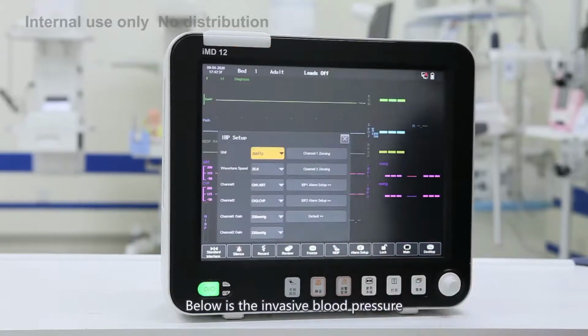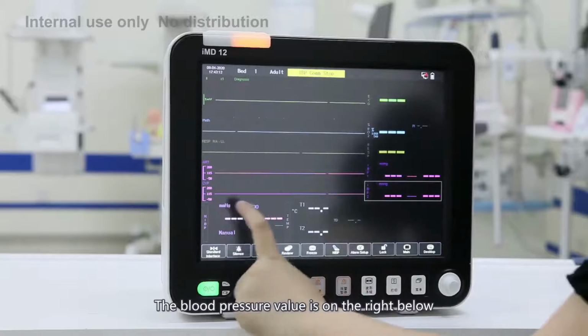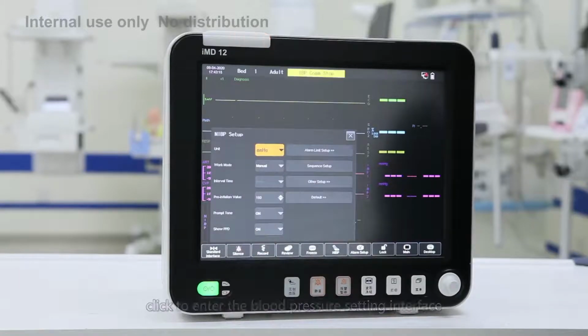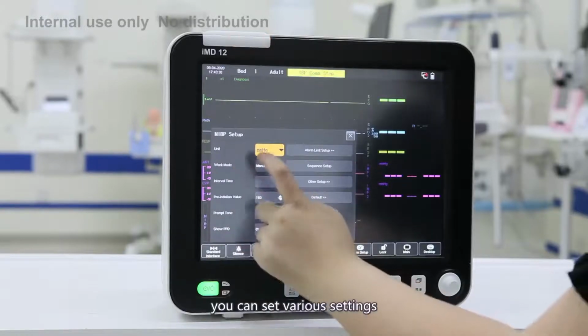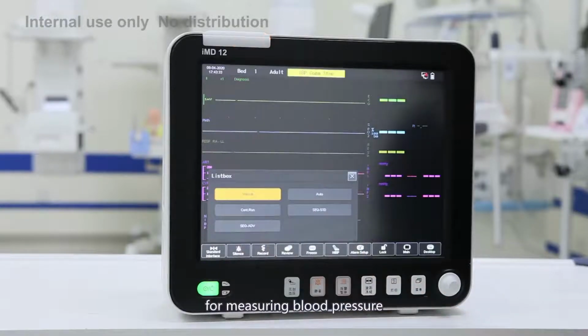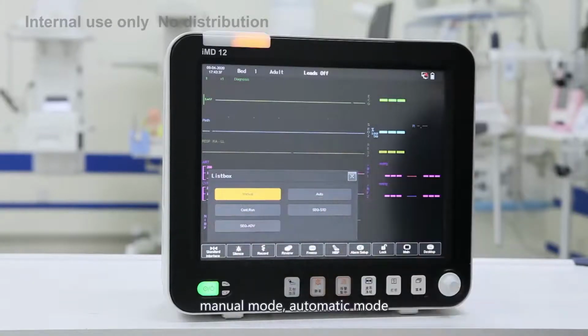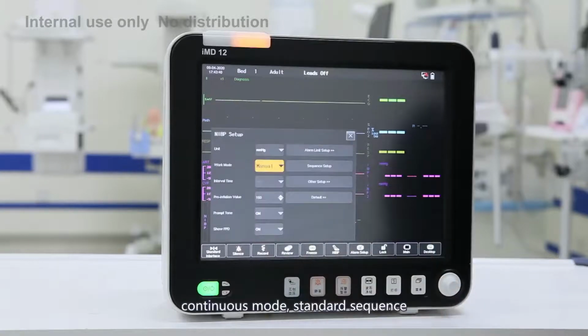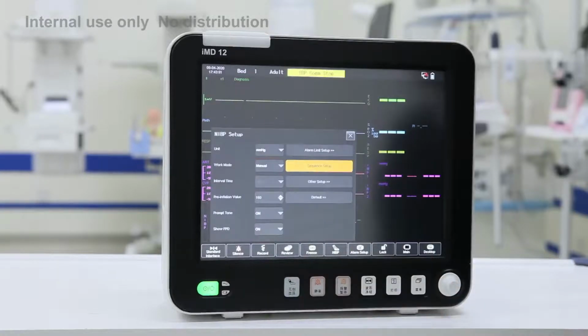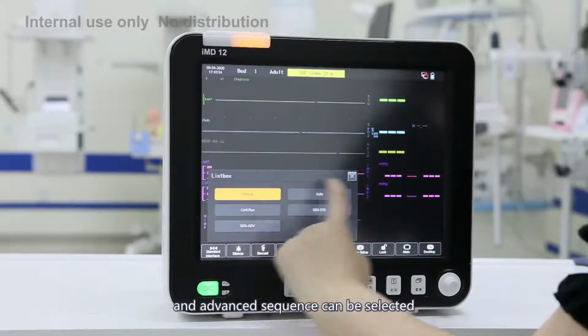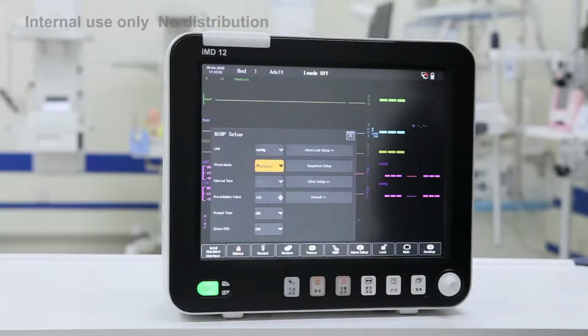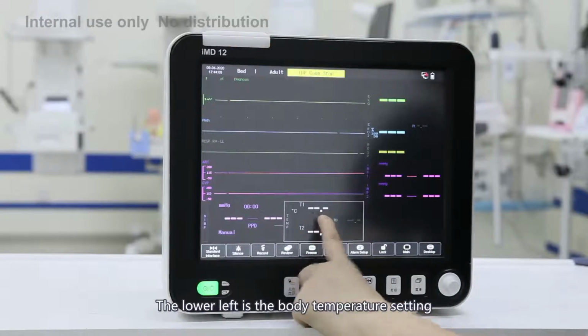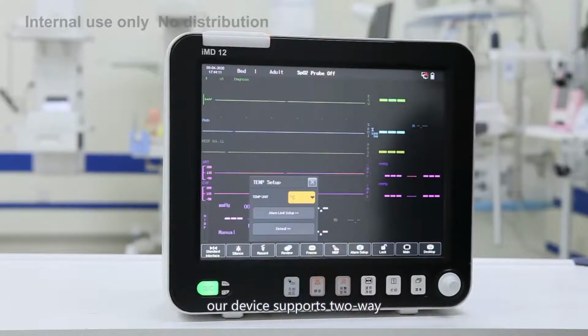Below is the invasive blood pressure. The blood pressure value is on the right below. Click to enter the blood pressure setting interface. You can set various settings for measuring blood pressure. In the measurement mode, manual mode, automatic mode, continuous mode, standard sequence, and advanced sequence can be selected. The lower left is the body temperature setting. Our device supports two-way body temperature measurement.